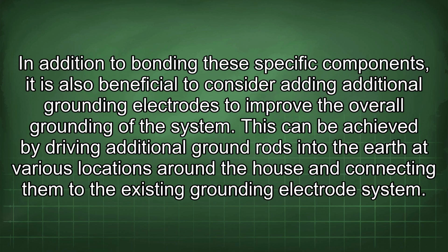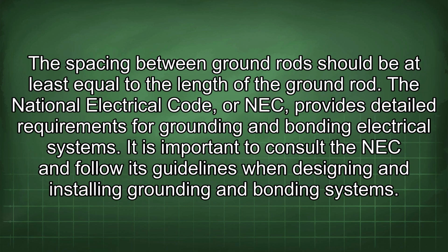In addition to bonding these specific components, it is also beneficial to consider adding additional grounding electrodes to improve the overall grounding of the system. This can be achieved by driving additional ground rods into the earth at various locations around the house and connecting them to the existing grounding electrode system. The spacing between ground rods should be at least equal to the length of the ground rod.